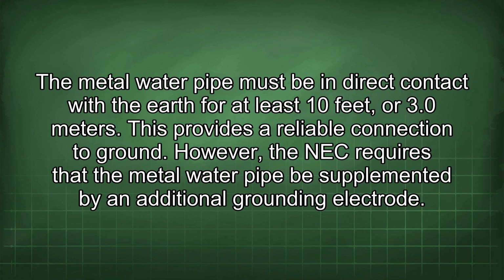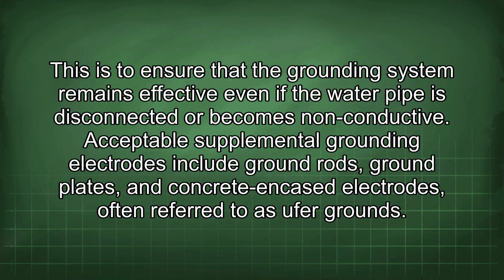However, the NEC requires that the metal water pipe be supplemented by an additional grounding electrode. This is to ensure that the grounding system remains effective even if the water pipe is disconnected or becomes non-conductive. Acceptable supplemental grounding electrodes include ground rods, ground plates, and concrete encased electrodes, often referred to as Ufer grounds.